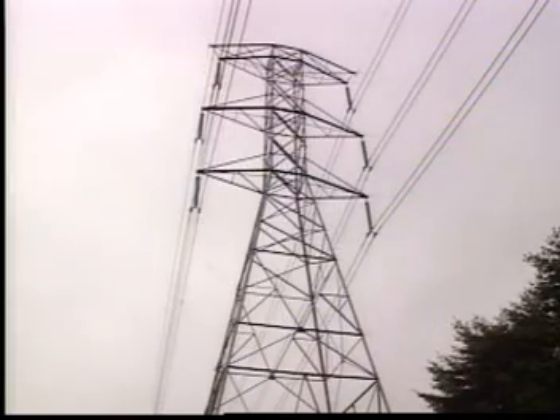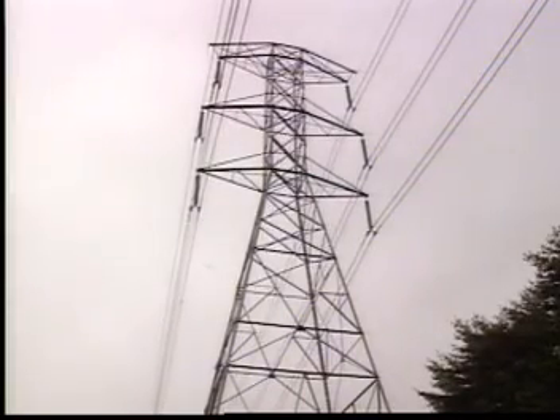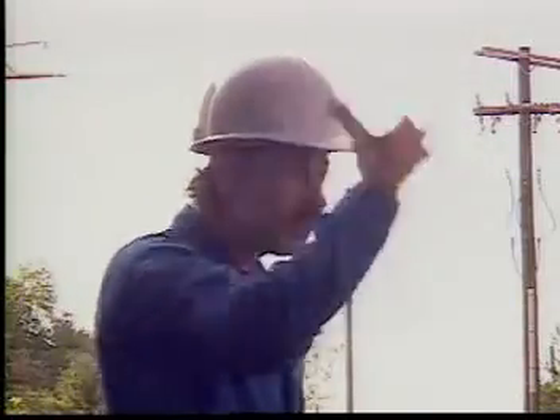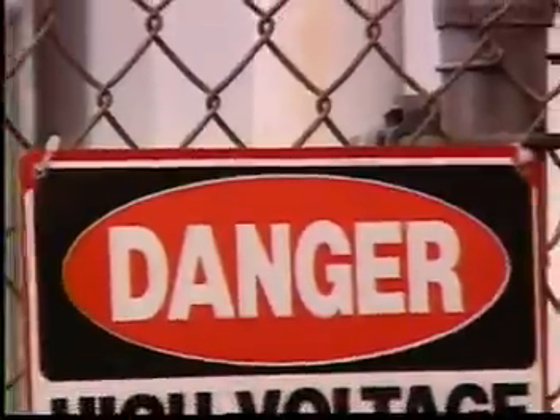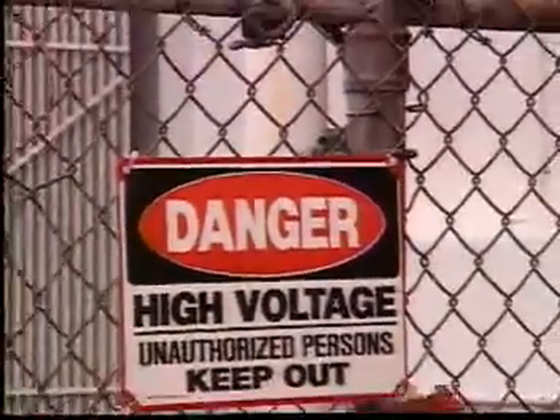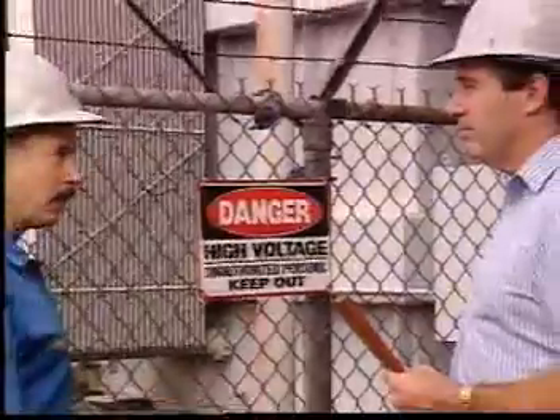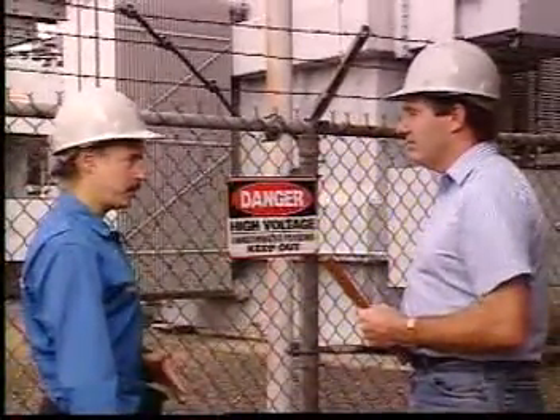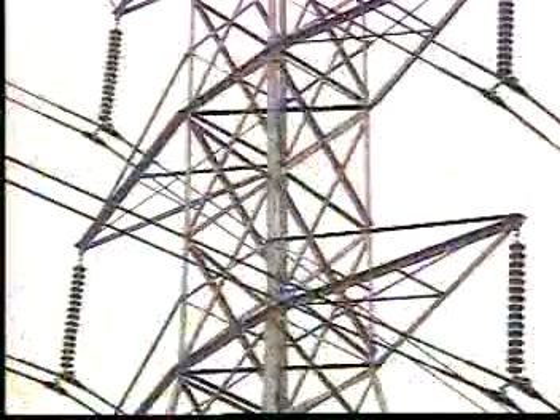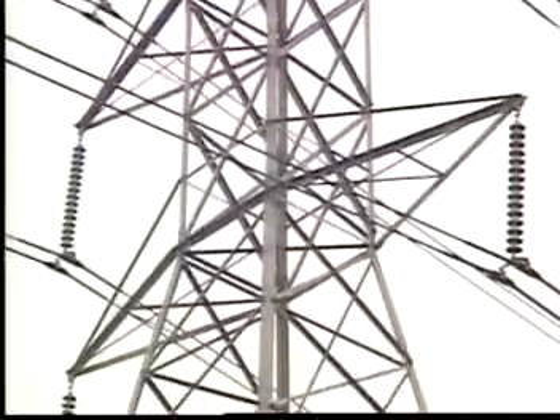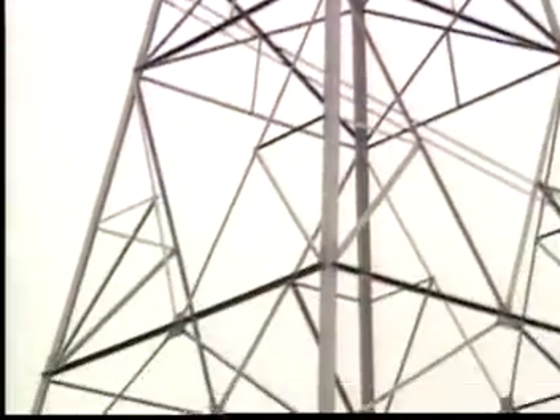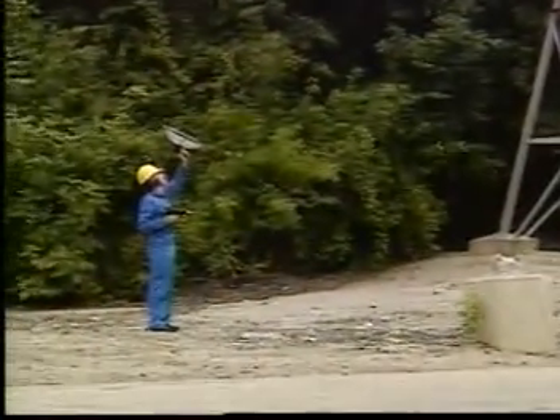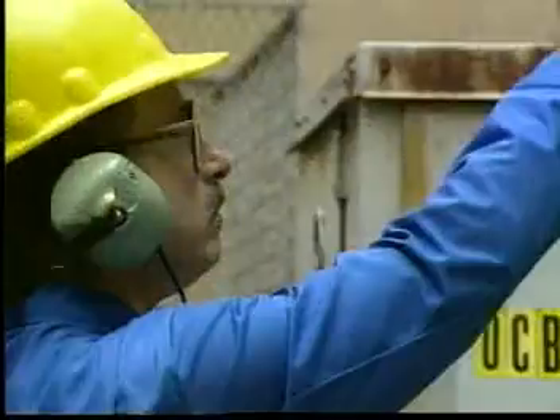We use the ultraprobe to scan cables operating at high voltages, so safety is a major concern. Never violate the integrity of metal-clad switchgear. If you are ever in doubt about safety procedures, consult with your supervisor. To test at a distance while maintaining excellent directionality for picking up ultrasound, we recommend use of the parabolic reflector, explained later in this program.